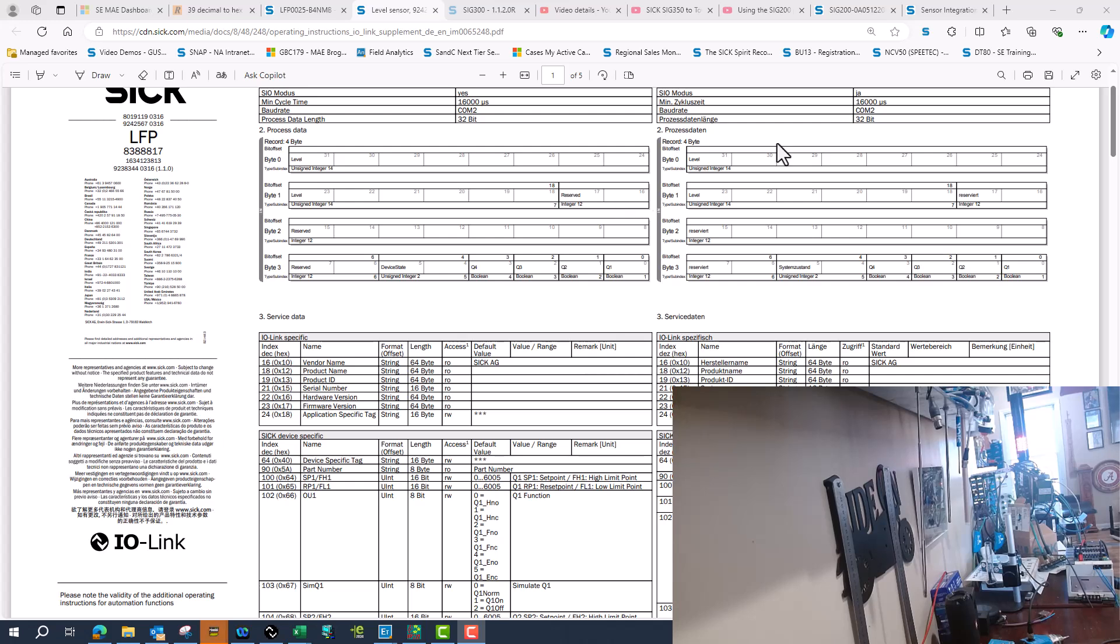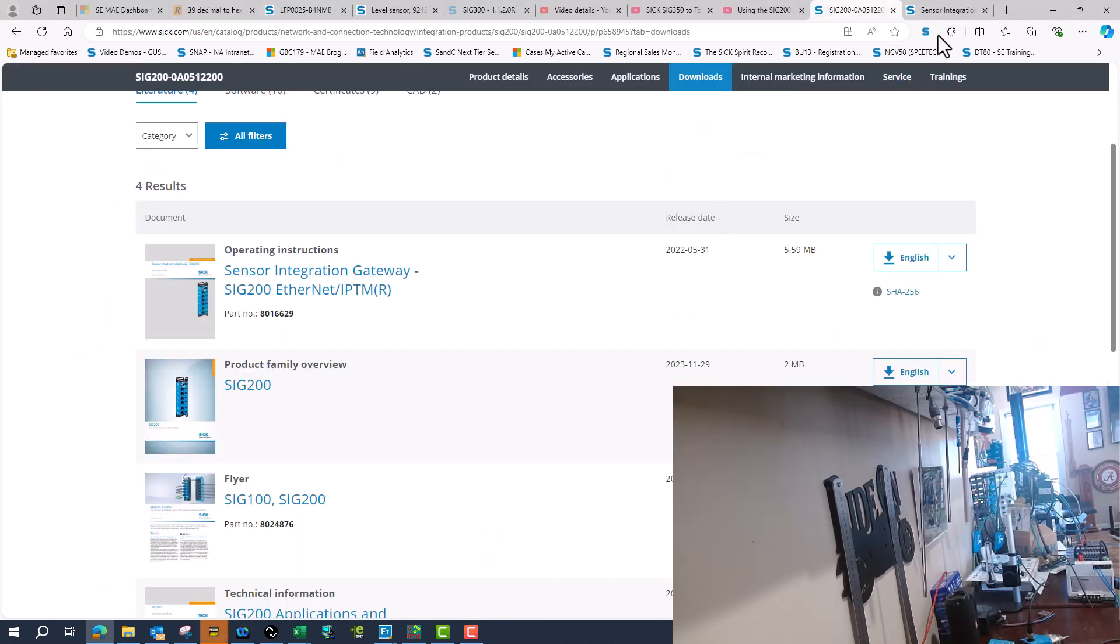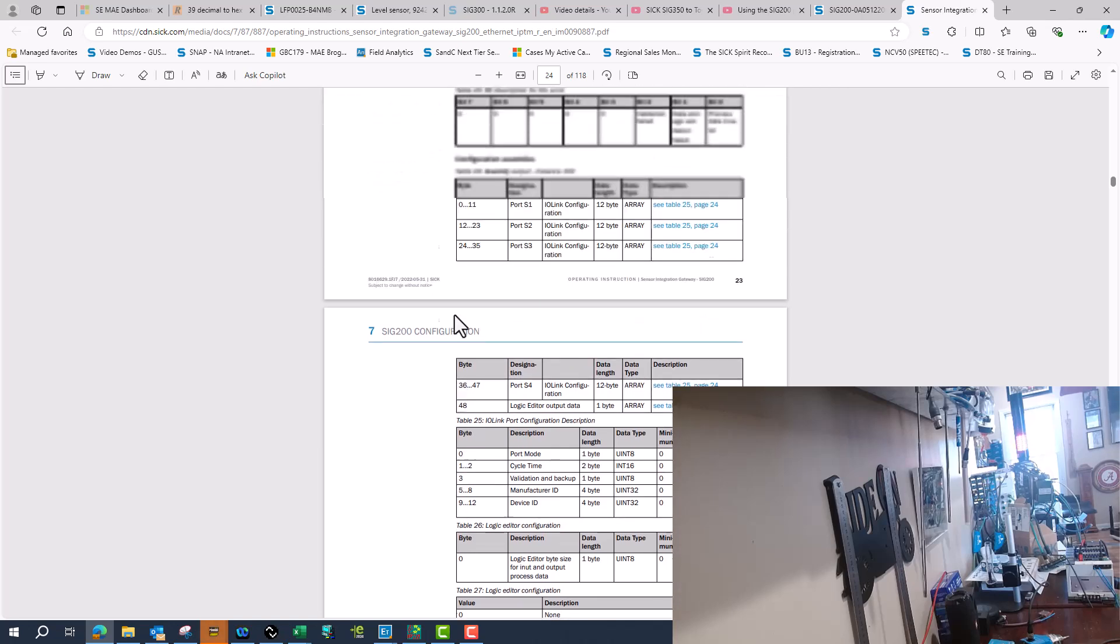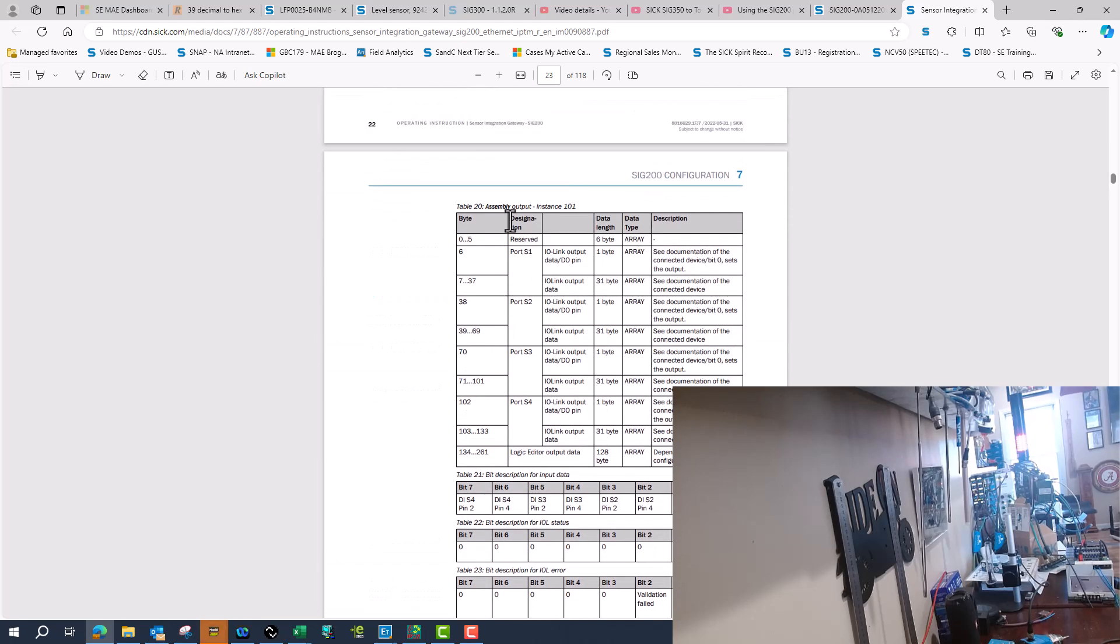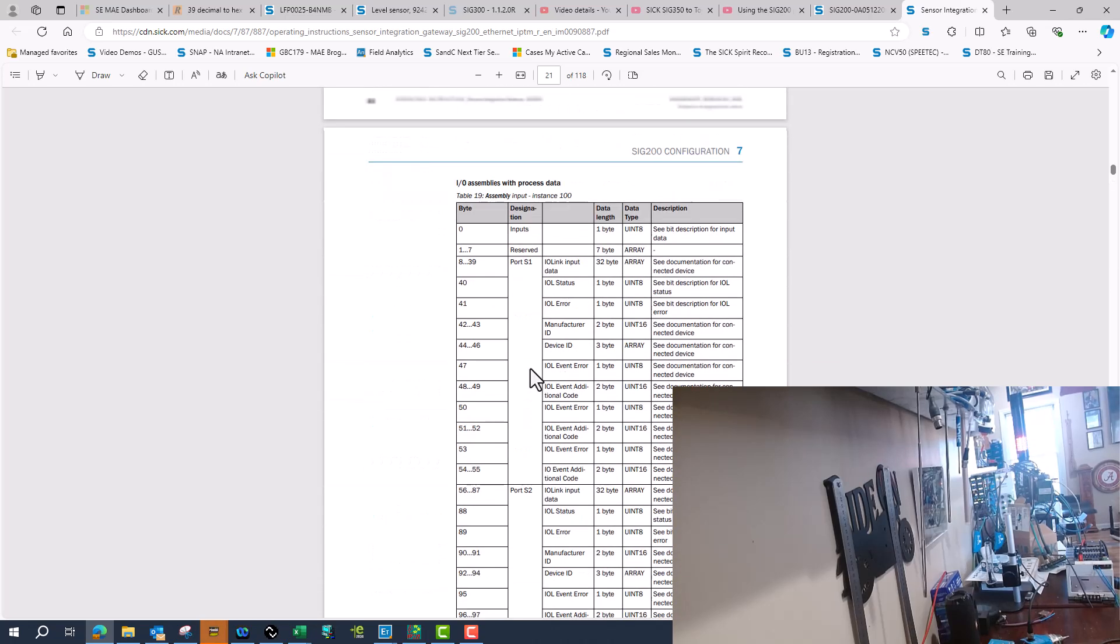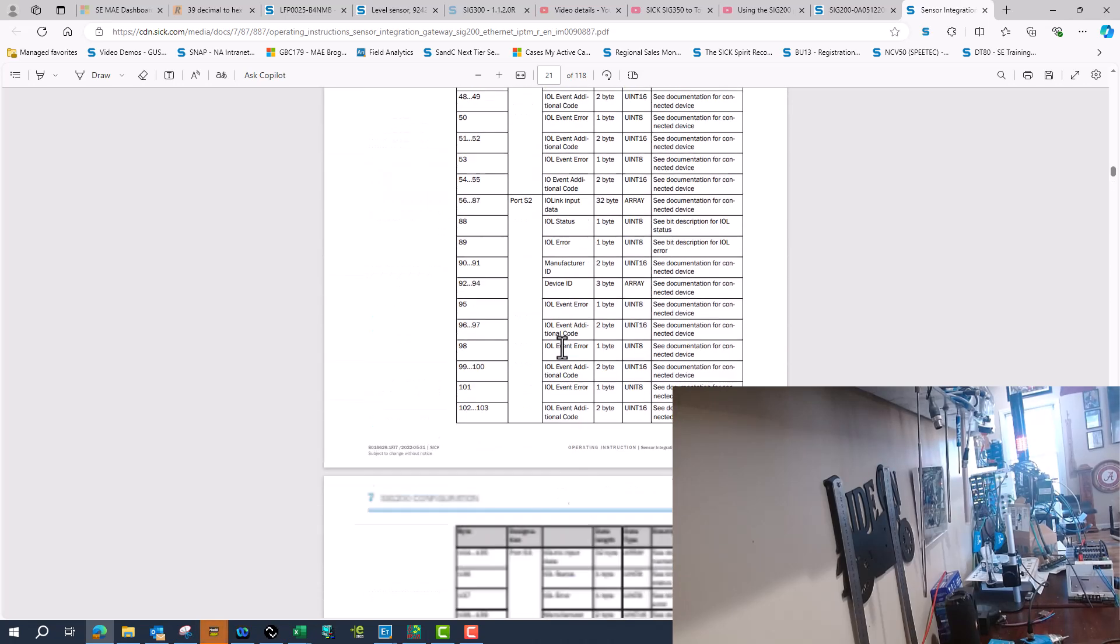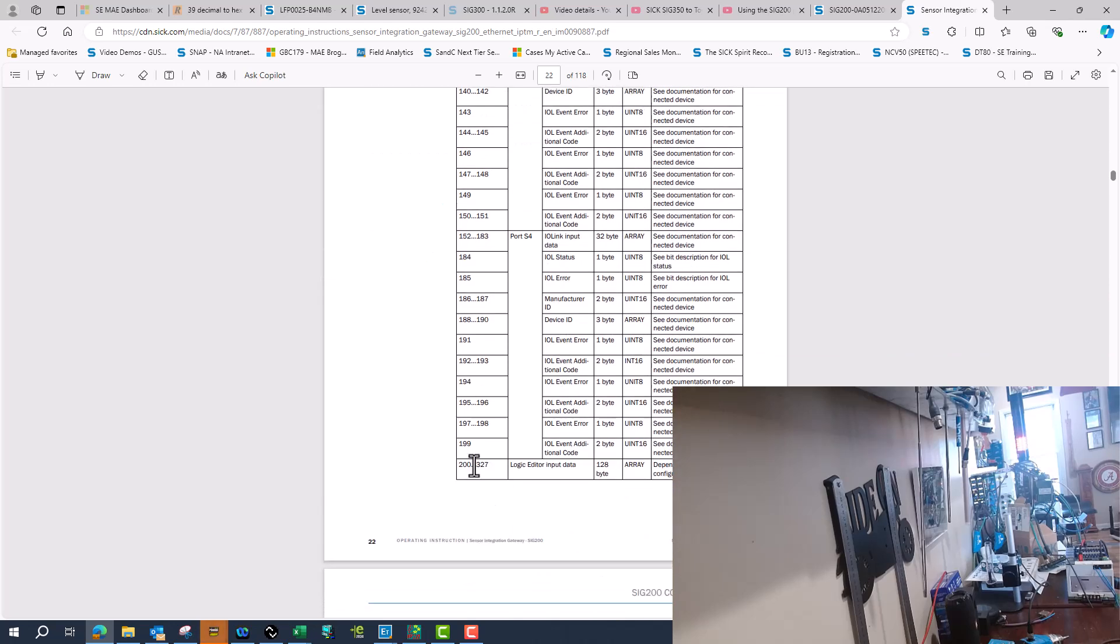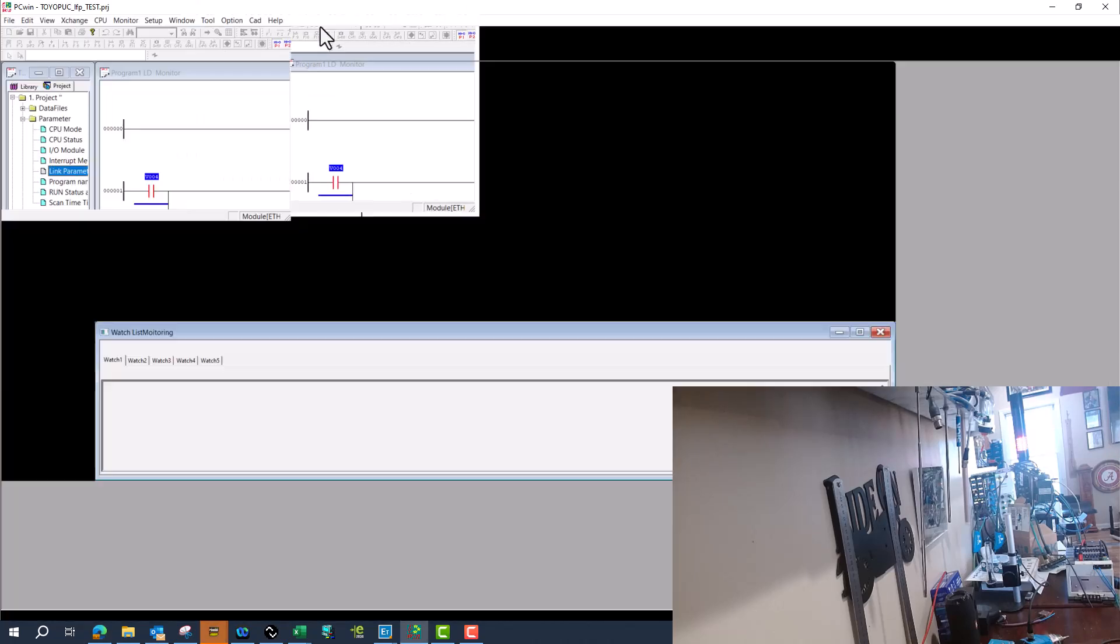So I'll just kind of go over what we need to understand. Since the ToyoPuc PLC will not take an EDS file, we need to understand the size of the produce and consume in our instance assembly. So I'll be using input instance or output instance 101 with a total of 262 bytes.